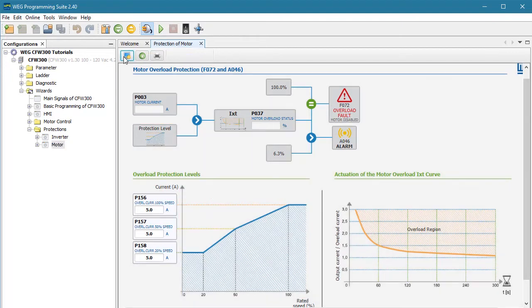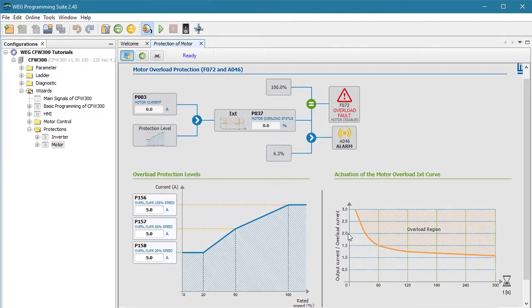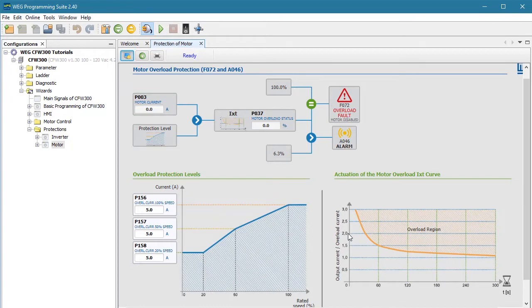We need to turn monitoring on for this to work of course. When you get this darker gray background like this, you know it's active. So step one is to monitor the current here while running your system at full load. Whatever amperes you read, add about 10% and put that here. You may want to tighten or loosen that for your system, but 10% is usually a good starting point.